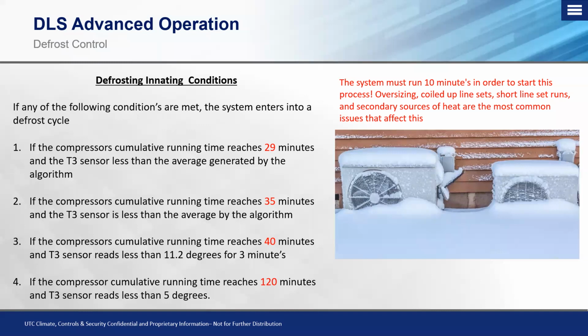And then the final condition on there is if that compressor's cumulative runtime reaches 120 minutes and the T3 sensor reads less than 5 degrees. Okay, you can see more runtime. Theoretically, the outdoor coil should be much colder, so it's going to look at that colder coil and also the runtime for the final initiating factor for defrost. Okay, so these are going to be the initiating conditions for defrost. But first and foremost, we need to understand we have to run at least 10 minutes before we start looking at that cumulative compressor runtime.